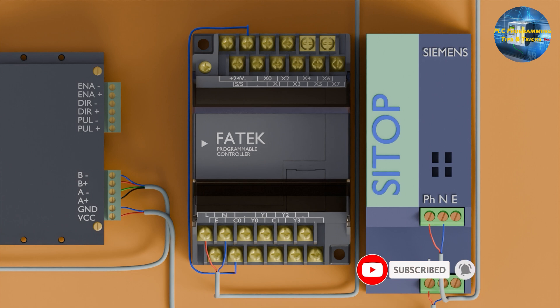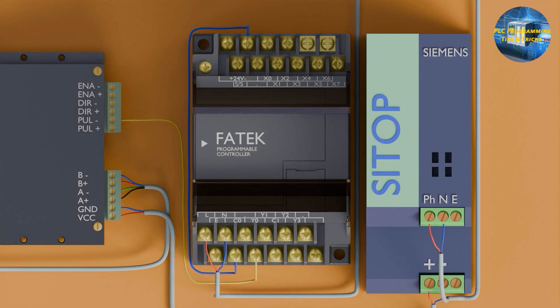Next, we will connect Y0 to the pulse input terminal of the stepper driver, and Y1 to the direction input terminal of the stepper driver. We will loop all positive input terminals of the stepper driver and connect these to the 24V positive output of the PLC supply. The wiring is now completed.